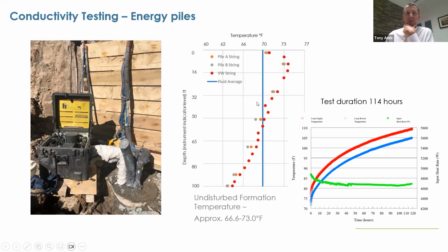What's useful here, in setting up and starting the system, is that we're going to be able to deliver a whole lot more heating to this system than we originally believed we could. Because the temperature difference between the ground and what's required in the building is so narrow, it's going to be super efficient. The idea is that over time, through the winter, we can drive down this heating by delivering more heat than the system is designed for. So we can swing this temperature profile down to where it should have been, so that in the summertime cooling season we've got a nice cooler ground temperature, closer to the temperature that's required in the building. Again, it's one of the most energy efficient means of delivering heating and cooling.